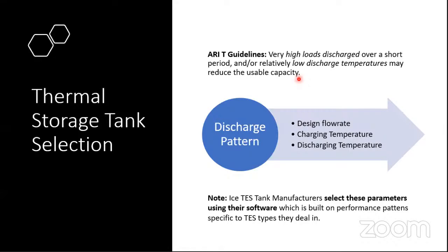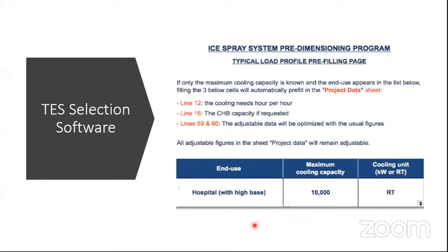This is how, on this basis, the thermal storage tank selection is done, and these parameters are selected using software which is built on the performance patterns of specific thermal storage types. These are different for different ice thermal storage tank manufacturers, or I would say technologies. For different technologies, they are different. To show you a glimpse of some software selection, this is a selection for an ice spray system, in which first the application is entered, what is the building type and what is the cooling load, and whether the unit is selected in kilowatt or tonnage.